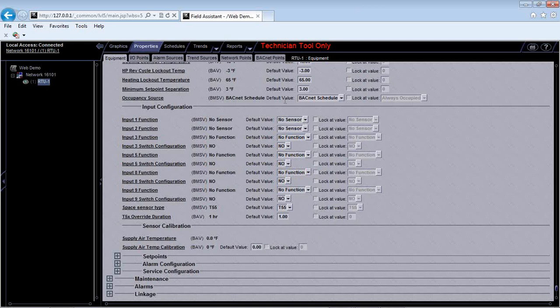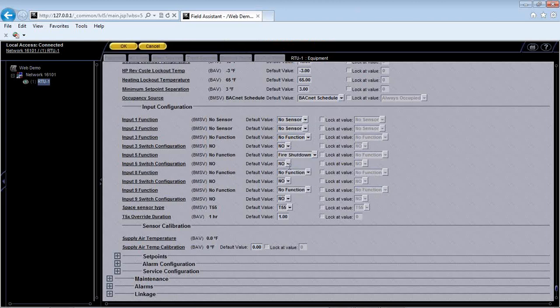Remote occupancy is, we talked about the occupancy source. If you choose remote occ input, you actually have to tell the controller what input to look at for that remote occupancy. There's one in the install manual that says to use standard, but you can actually use any of these 3 through 9 inputs. And then one other thing to look at is for this input, you can actually tell it if it's a normally open or normally closed input. So if you wire an enthalpy, or if you have a fire shutdown that's normally closed, wired in normally closed, if I leave this as normally open, I'm going to read that I'm in fire shutdown because my contact's going to be closed. I need to make sure that I switch this to normally closed, or else I'm not going to be able to run the unit because I'm going to think I'm in fire shutdown. Okay? I'm going to hit cancel here.